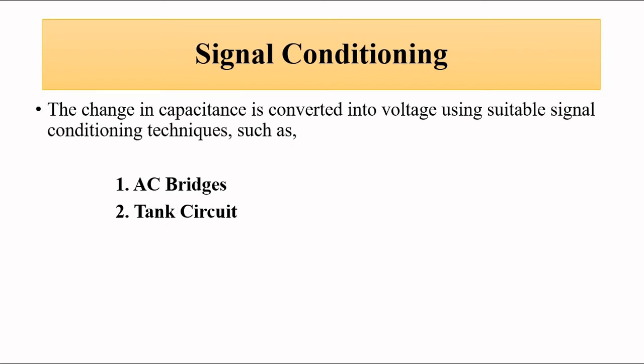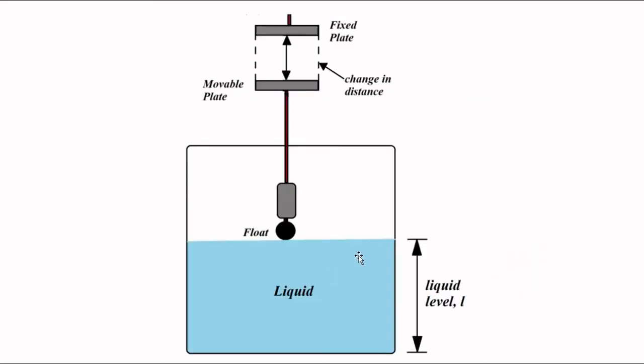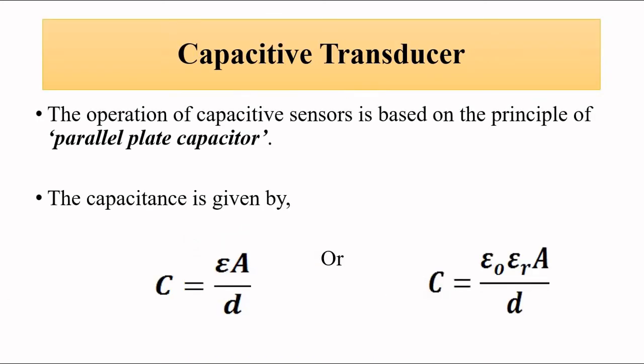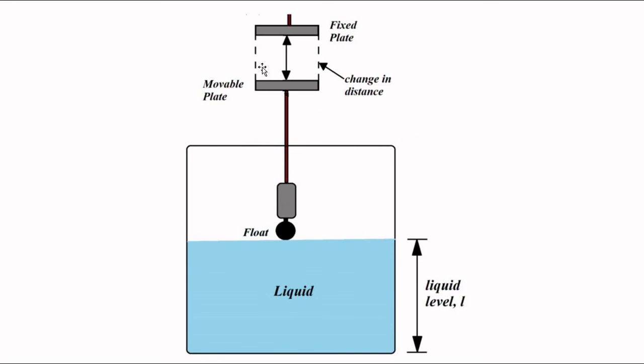In the first capacitive sensor method we previously discussed, the change in relative permittivity of the medium was taken into consideration — two capacitor plates were connected at two ends of the tank, and as the liquid level rose, the relative permittivity of the medium between the plates changed, causing capacitance to increase or decrease. In this current method, the parameter undergoing change is the overlapping area (first arrangement) or the distance between the capacitor plates (second arrangement).